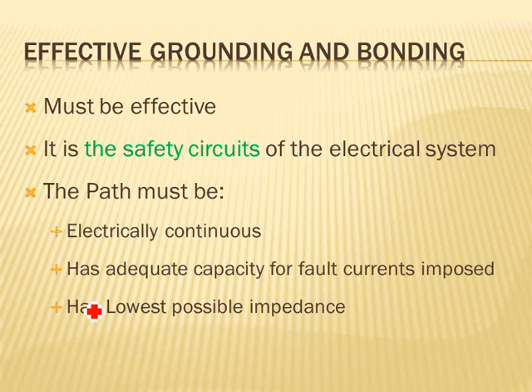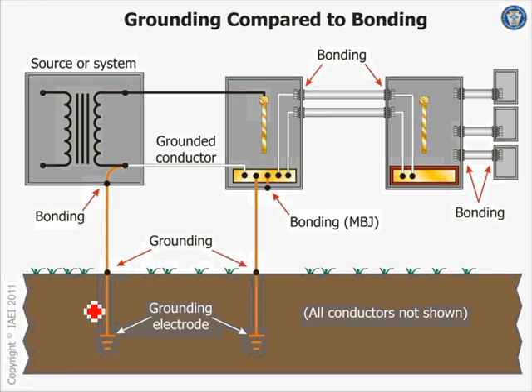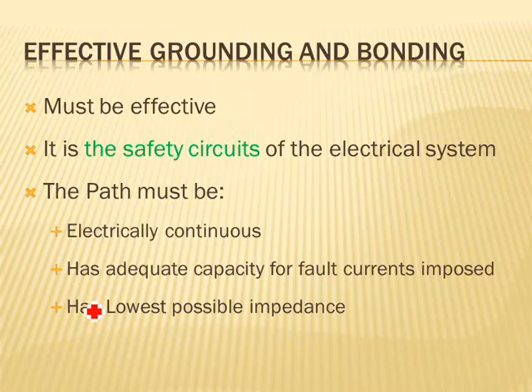Okay, effective ground path. Why do we care about it? They keep talking about the effective ground path, taking it from here through this conduit, through the frame, through here, back here. Here it takes what I call a free ride through the enclosure back to the source, versus going back to Mother Earth. That path must be effective. It is the safety circuit. That circuit acts under abnormal conditions. Under normal operating conditions, your equipment grounding conductor is doing nothing.